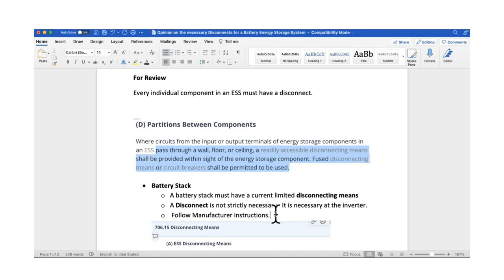So here's the scenario that we're concerned about. For example, let's say you have a Generac where there is one line that feeds the Generac that just goes to the grid, and that's the one that normally runs and is normally on. But you have a second AC output off the inverter that just goes to your backup loads. Mm-hmm. All right. So if I, for example, threw the AC disconnect outside, then the other inverter, the other source would kick on and start putting power into the house. And the first responders are pretty sure that they've shut off the solar, but it's not, because there's still power to the main panel or the backup panel.